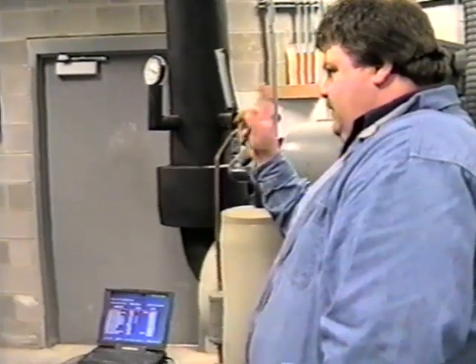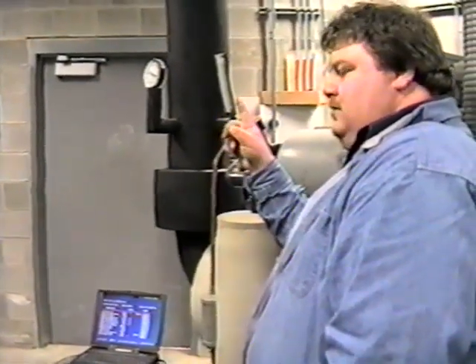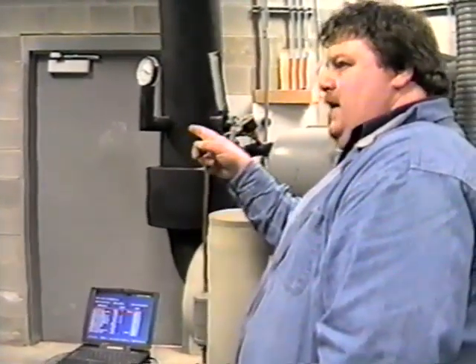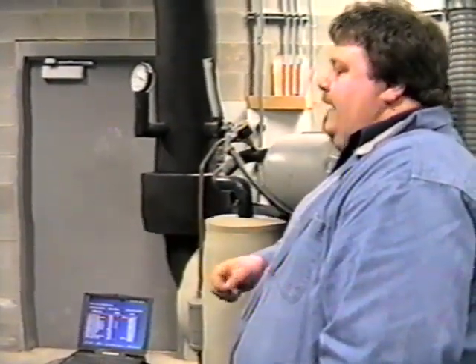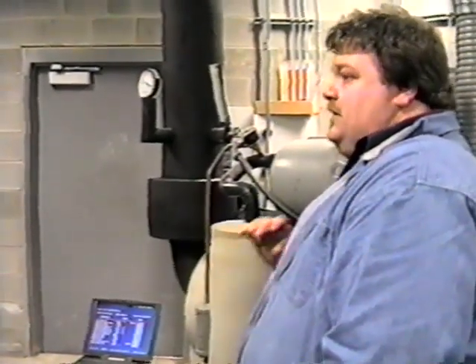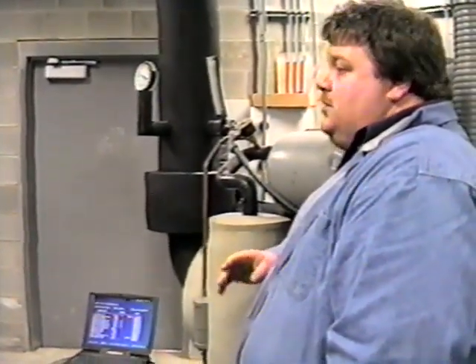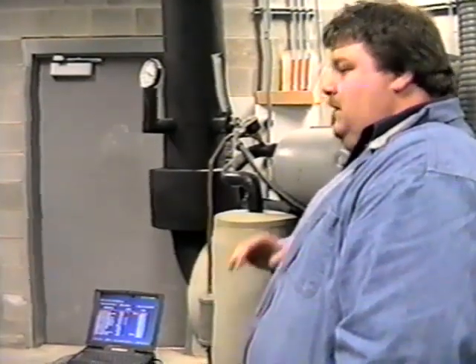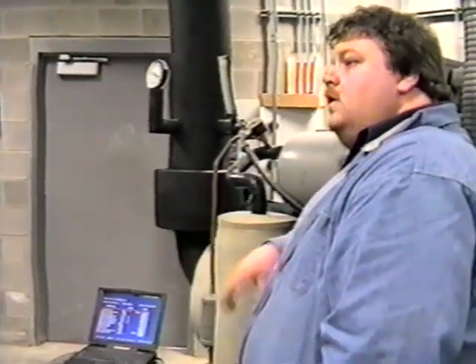Got an idea, it's 1 minute or 5 minutes. The largest time delay is on the condenser water pump, which is the 10-minute. And that's in that panel, there's a timer. That's what Carrier wants. I'd like to see it shorter than that, but at this point, it's been working. So I'm like, let's leave it. Like I say, get all the bugs worked out, then tweak it if you want.